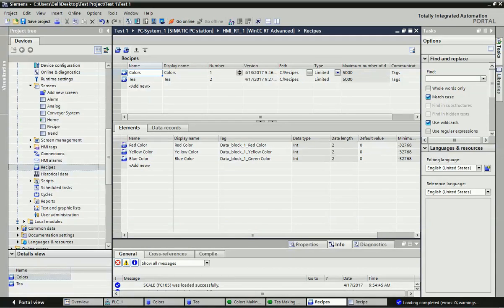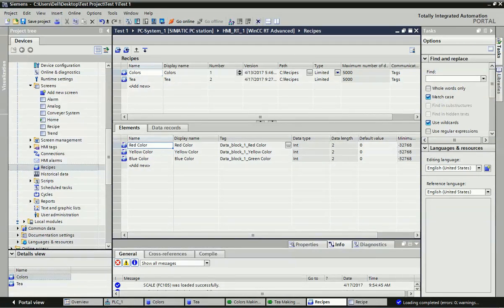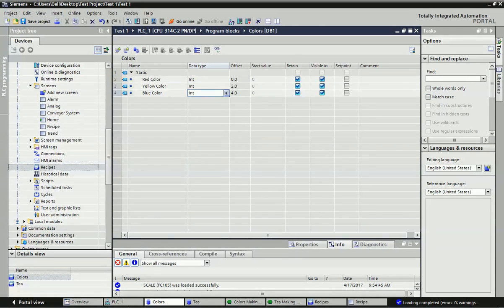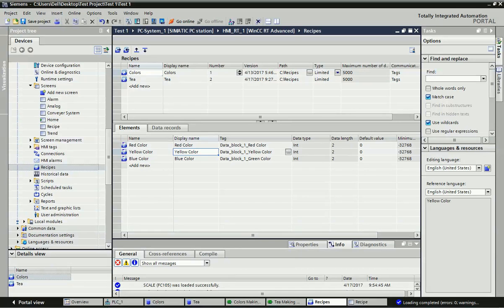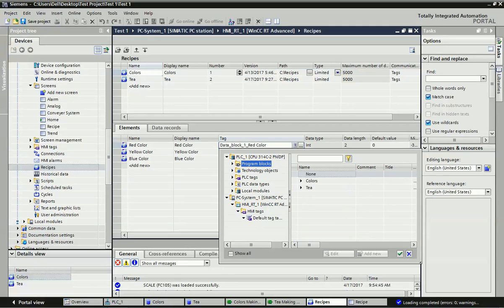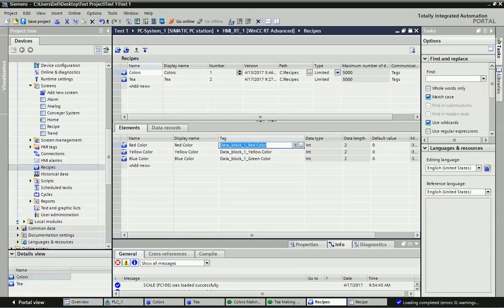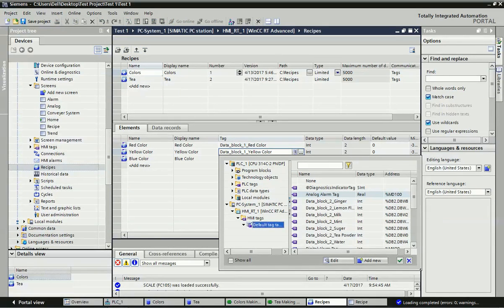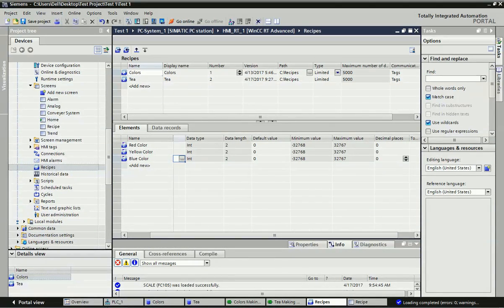I have added two recipe names: Colors and Tea - just two types of recipe. For the color recipe, I will add the same elements we have taken in the data block: red, yellow, and blue. The display name must also be the same. Now for the tag, I will connect the same tag from the data block. I will open the color data block and add the same elements - yellow connects to the yellow tag from the data block. I have added every element with its corresponding tag.